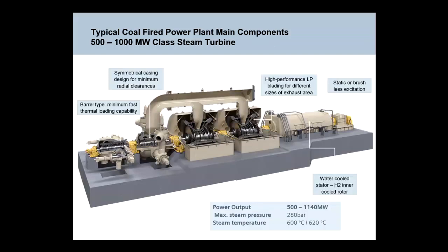So this cross-sectional picture shows a typical large utility steam turbine. There is a high-pressure cylinder here with control valves. The steam is then expanded through the high-pressure cylinder. This is all on one shaft, taken away to the boiler, reheated, brought back to this intermediate pressure cylinder, expanded. It comes up and flows, in this case, to two low-pressure cylinders. You can see the turbines are getting bigger as the steam expands and the pressure is lower because the volume increases. The steam expands through these two turbines and then drops out to the condenser, which hangs below the two LP turbines. All of that shaft is then driving this generator at the end of the machine. So that's a typical large utility steam turbine.